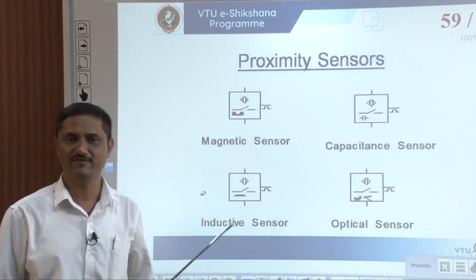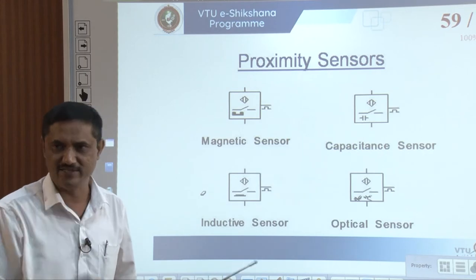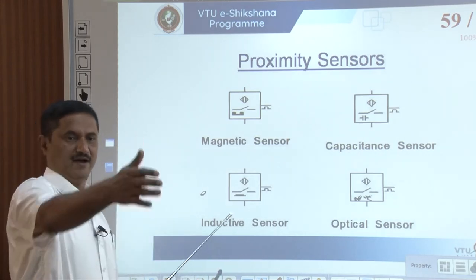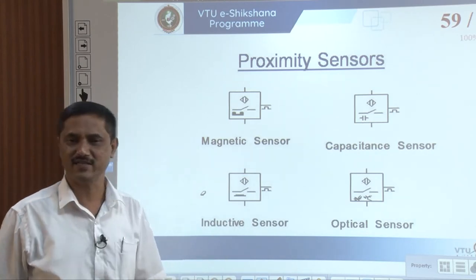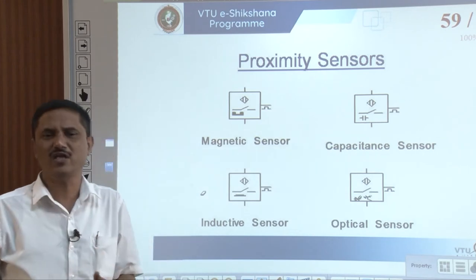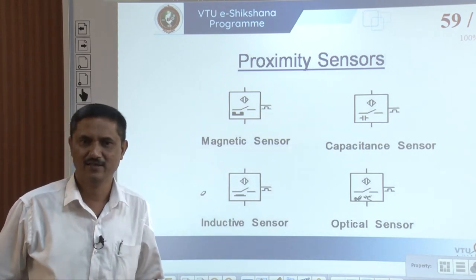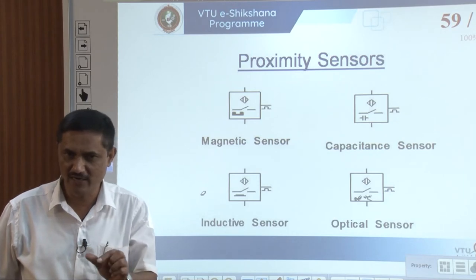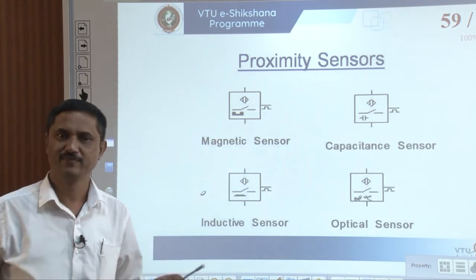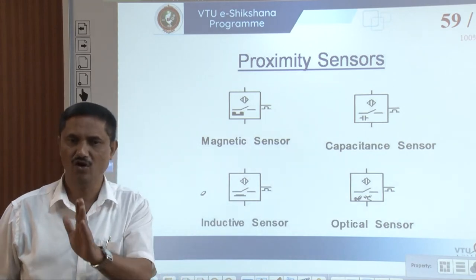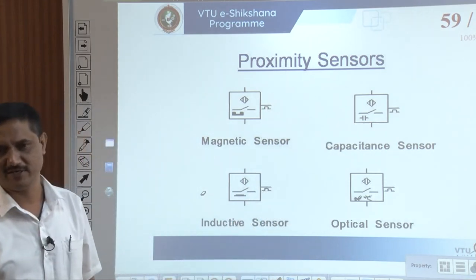Another important parameter of inductive sensors is high switching frequency — meaning on and off ability. In one second, inductive sensors can switch 1500 times and still work. This is an advantage for counting applications — number of counts or rotations. The second characteristic is switching frequency, and the third is switching distance — how close you need to bring the object to the sensor. This comes under the proximity sensor category: the object must come very close to the detecting element, say 50 to 60 millimeters. The switching distance depends on the diameter-to-length ratio of the sensor. Ultimately, this is not a long-range sensor; it is a proximity sensor.